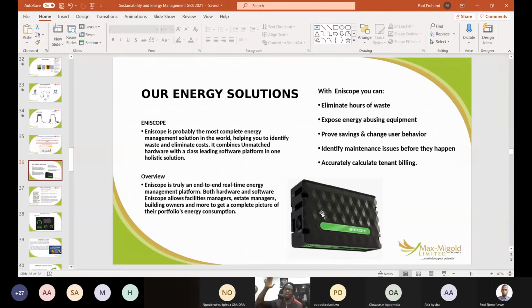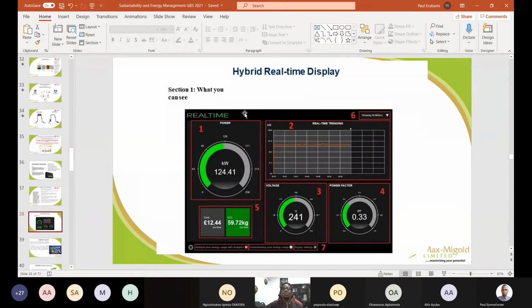I go to each of the floors where you have the distribution boards - your 12-way, 16-way, 32-way dBs - and install one of these beside them, metering every important load. If I want to meter every load, lights, sockets, everything, I label all of them on the dB and inside the software, so that when I check the back end, it tells me what circuit this is.